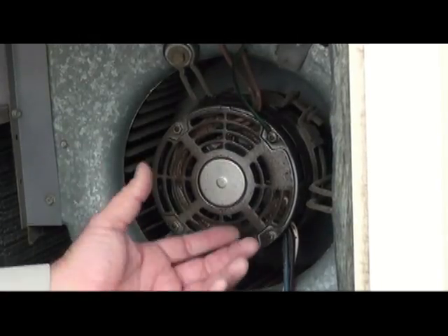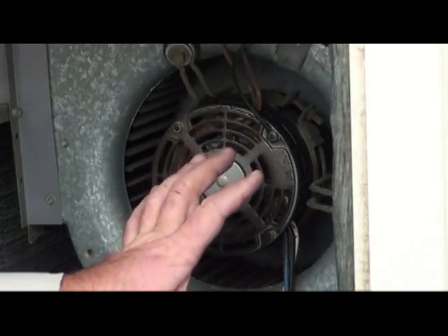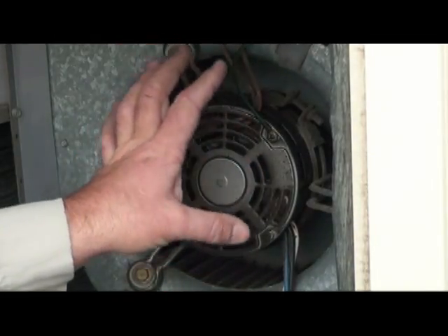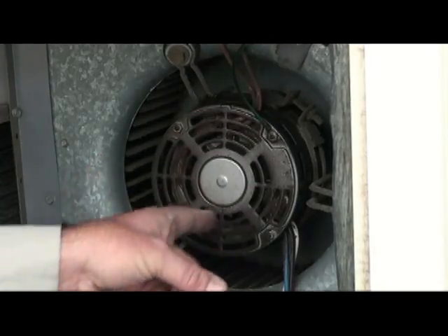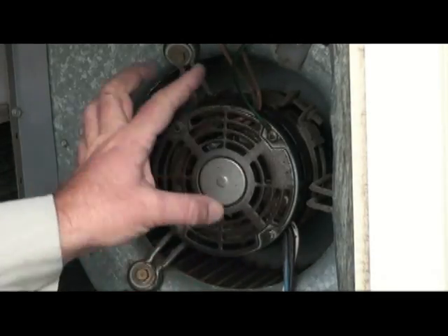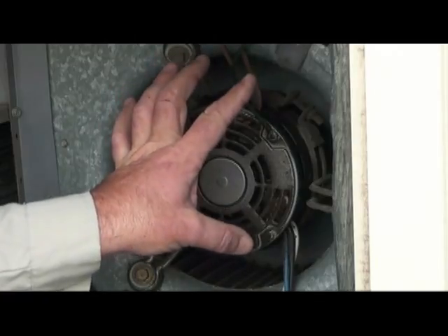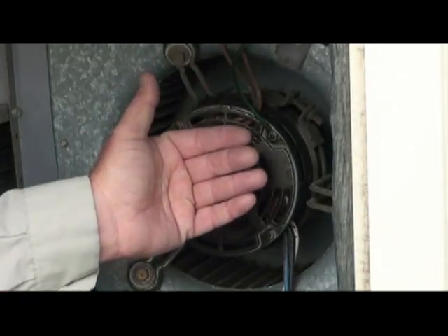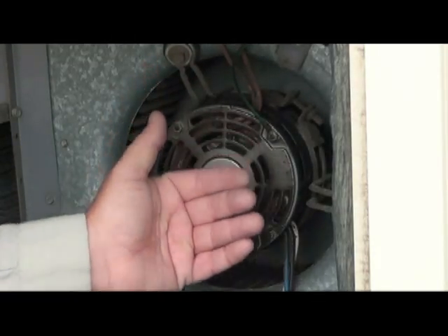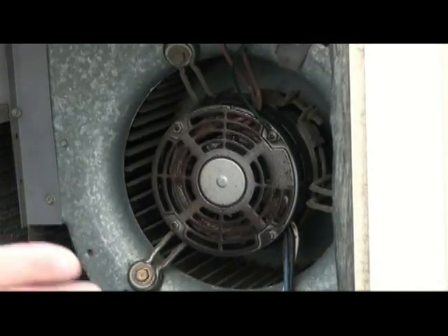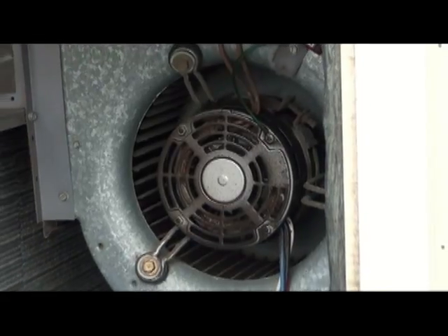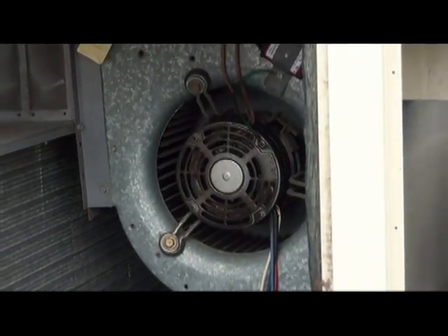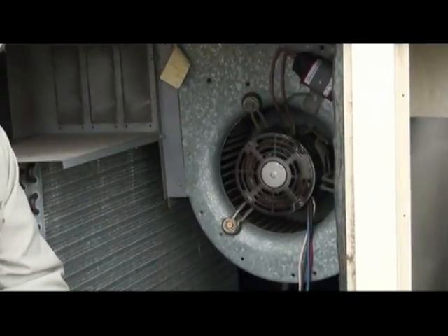The third failure on these motors is just the motor itself being dirty. A lot of times you can see how the motor is opened here at the end of the motor. This allows this motor to breathe and cool. When dirt builds up on this motor from running time, the dirt actually insulates the motor from being able to cool itself. And that in itself will cause problems. That causes that motor to run hot, which causes the amp draw to go even higher at that point.